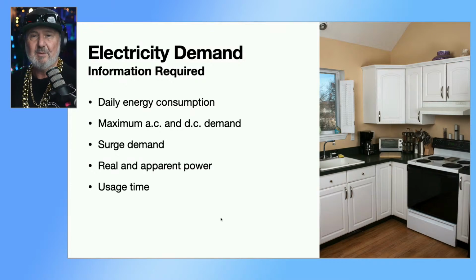Surge demand is about understanding the problem appliances, and particularly what we call simultaneous or coincidental surge demand. For instance, you might think the pump surges up to like 3,000 watts when it starts, so that's the only one we need to consider. But actually, the pump surges because you've got the washing machine on, and the washing machine's got a heating element in it, so the two will be coincidental demand. Looking at what those might be will affect your inverter size selection.